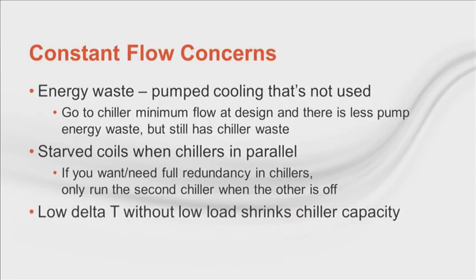And DeltaT is the only way to load the chillers. While we do expect lower DeltaT at part load, if it's due to a system problem, it may not track well with load. When this happens, you lose system cooling capacity. Release chilled water reset and look for your worst offending coils to improve system DeltaT. We'll come back to this in a few minutes. But for these reasons, primary-secondary systems became popular. These systems are also called decoupled systems.